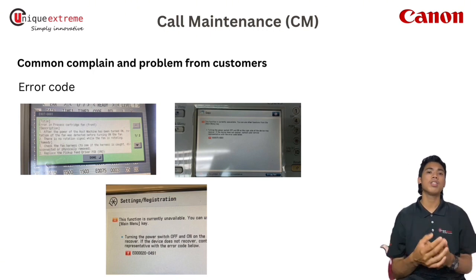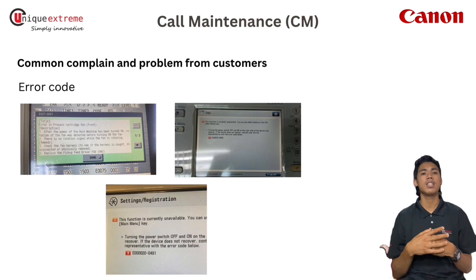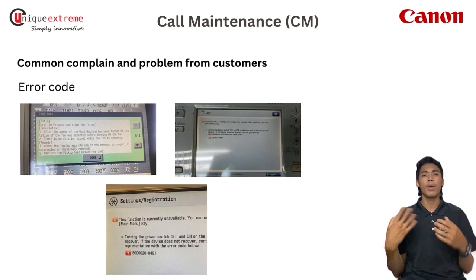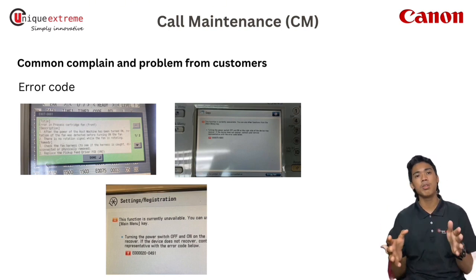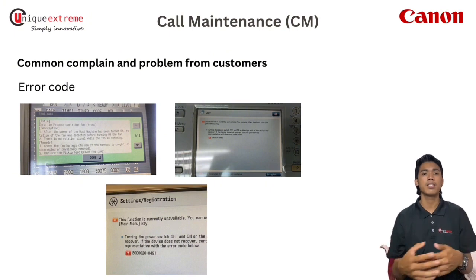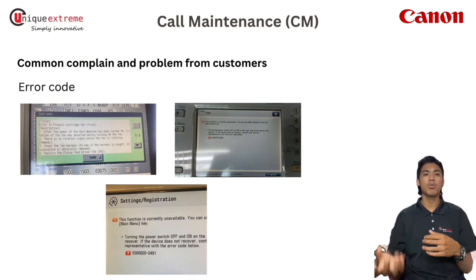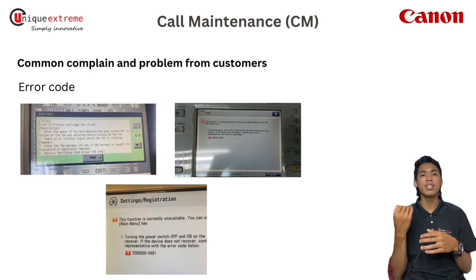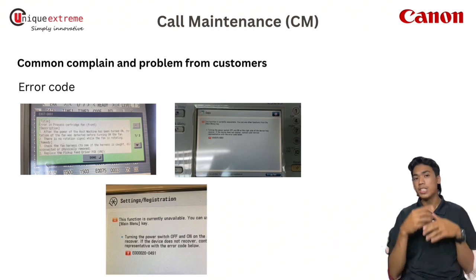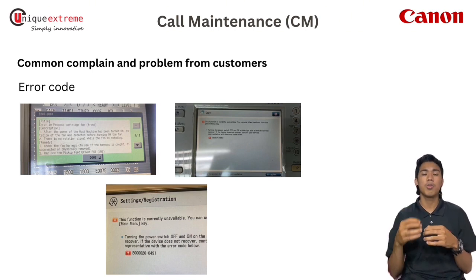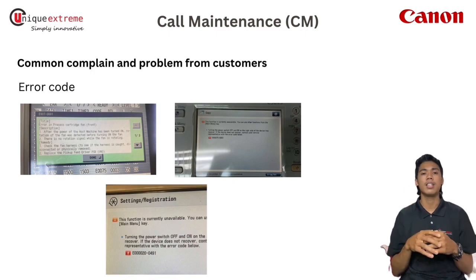Next, error code 75 usually represents an error in the ITB unit. The belt might not be balanced, so we need to service the ITB unit and rebalance the belt in the ITB unit. For error code 20, usually we will know there is an error in the developer unit but need to check which color, so we just need to replace it with a new one based on the color.